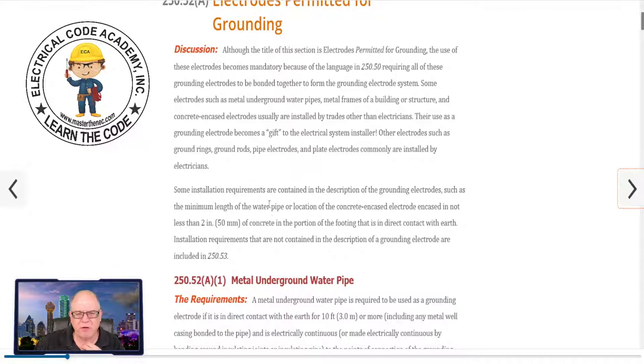Some installation requirements are contained in the description of the grounding electrodes — such as the minimum length of a water pipe, again 10 feet in contact with the earth, or the location of the concrete encased electrode and not less than two inches of concrete. So the concrete encased electrode, whether it's the rebar or four-gauge copper, has to be enveloped in at least two inches of concrete in the footing that is in direct contact with the earth. That's key — because if there was a plastic or vapor barrier where that footer was not directly in contact with the earth, then you don't have a Ufer ground.